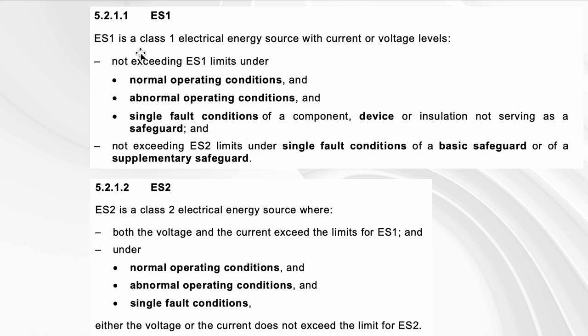ES1 must not exceed its limits under normal and abnormal operating conditions, and also under a single fault condition — but not of a safeguard. If there is a single fault condition but no safeguard has a single fault condition, it must not exceed ES1.